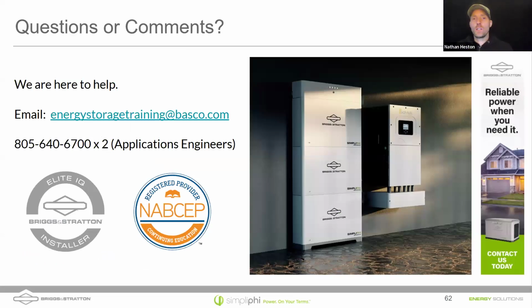Daniel, are there any questions in the Q&A for us? Yeah, so Chris mentions, it's more of a comment. Please note that Tigo rapid shutdown devices system will keep the panels off after a low battery shutdown. So you can't depend on the array to recharge the battery. Without a generator, you have to overcome the Tigo by providing it with an alternative power source, for example, a portable power supply. Problem that I've run into, yes. Then the Tigos will allow the panels to produce. Go ahead. So you could use something like, I have a UPS right next to me here.